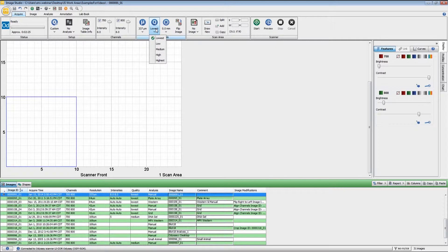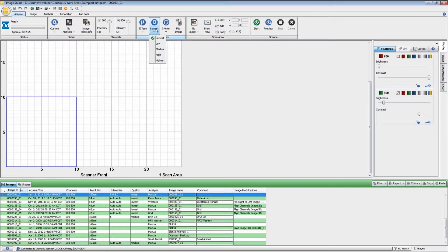The next setting is the quality, and the default setting is lowest. The reason for that is the lowest quality will give you the fastest scan speed. If you go with a higher quality, it will give you a minor increase in your signal to noise, but generally you will not notice any difference, and it does have a fairly major effect on the scan time. So just to get the fastest scan, we do recommend that you go with lowest.